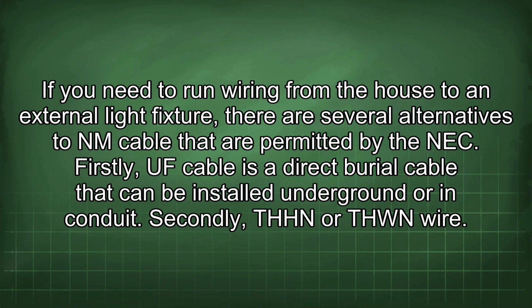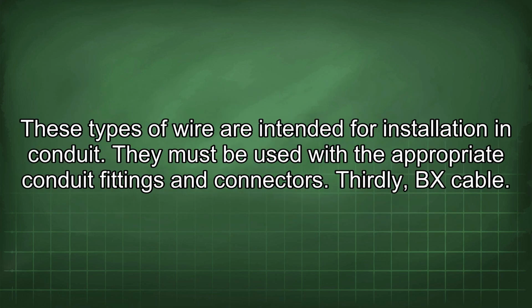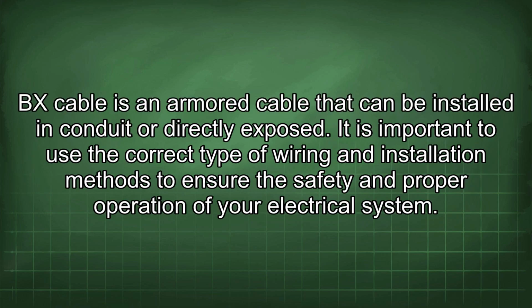Firstly, UF cable is a direct burial cable that can be installed underground or in conduit. Secondly, THHN or THWN wire. These types of wire are intended for installation in conduit. They must be used with the appropriate conduit fittings and connectors. Thirdly, BX cable. BX cable is an armored cable that can be installed in conduit or directly exposed.